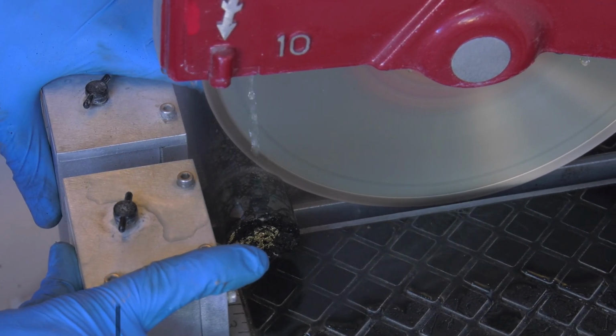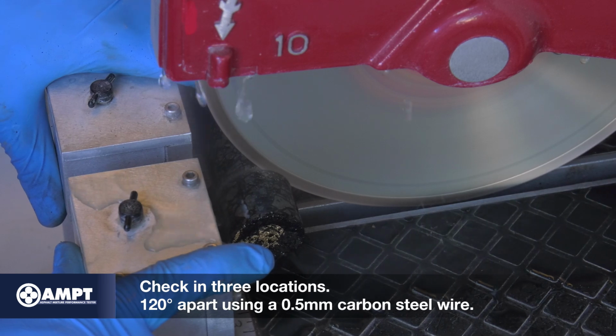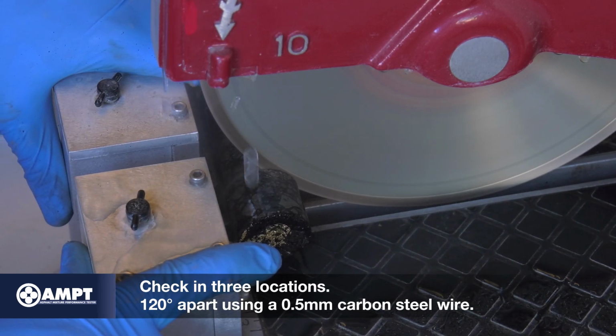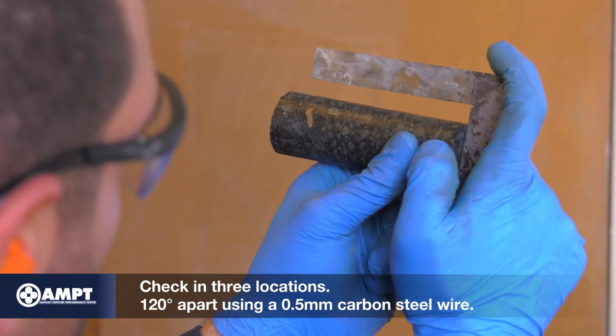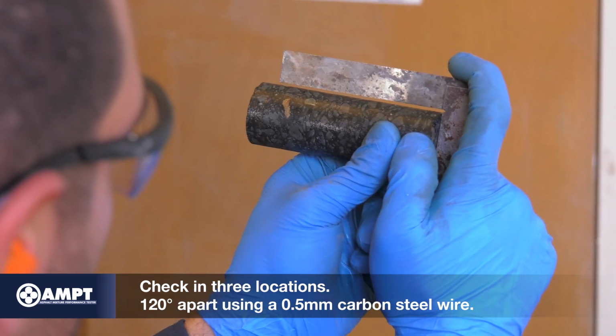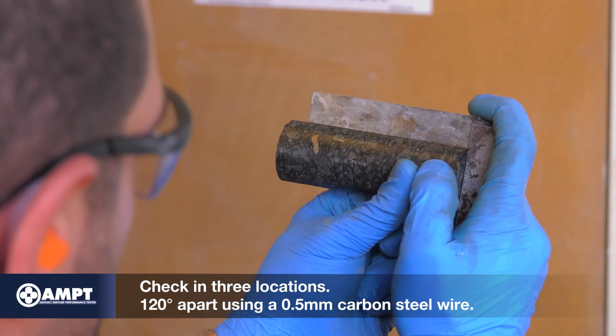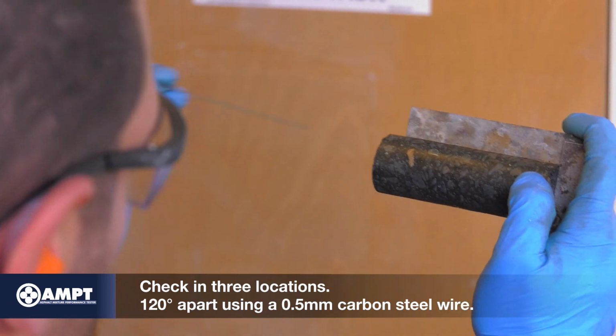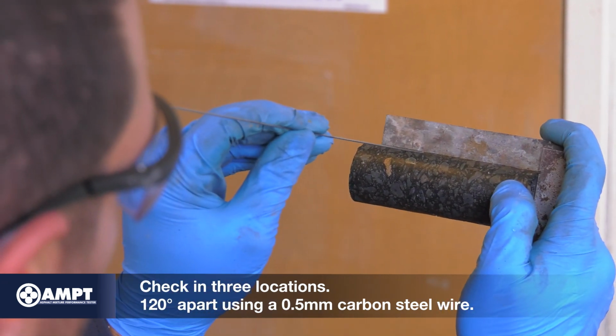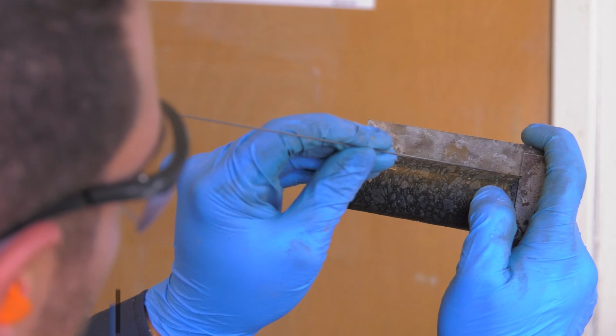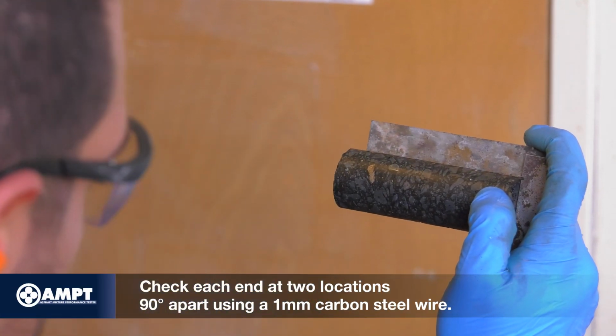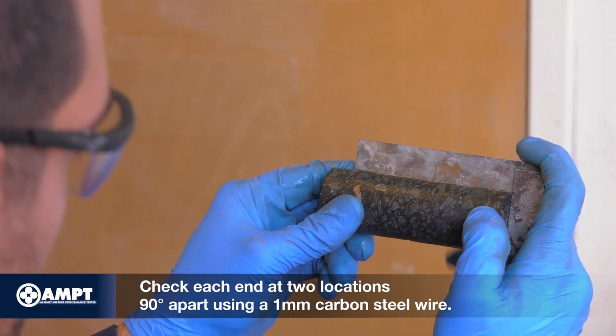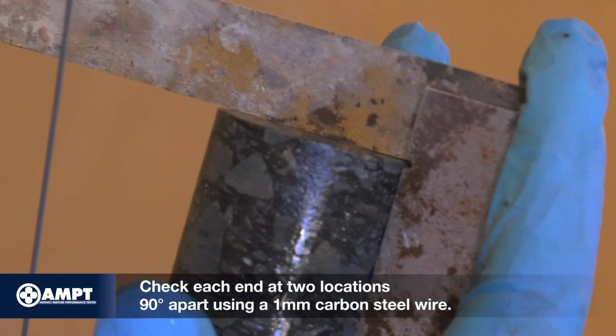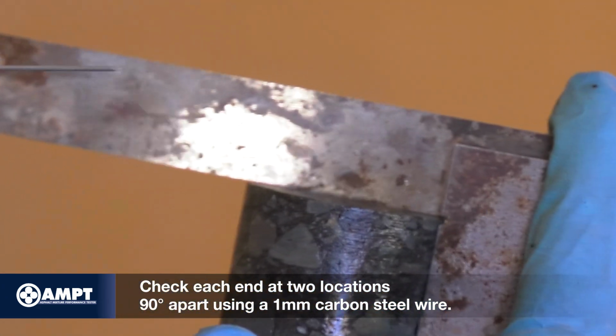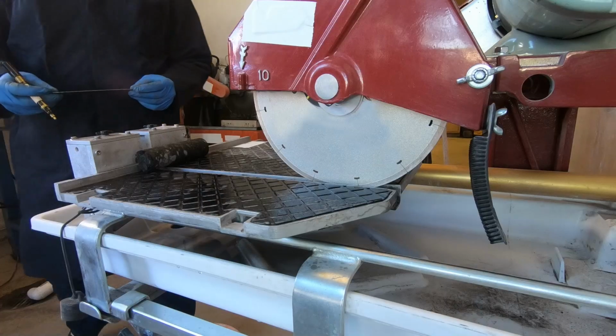Check the flatness of each end at 3 locations, approximately 120 degrees apart. Using the blade of the precision square as a straight edge, check the maximum departure of the test specimen using a 0.5 mm diameter carbon steel wire. Check the perpendicularity of each end of the specimen using a precision square and a 1 mm carbon steel wire at 2 locations approximately 90 degrees apart.